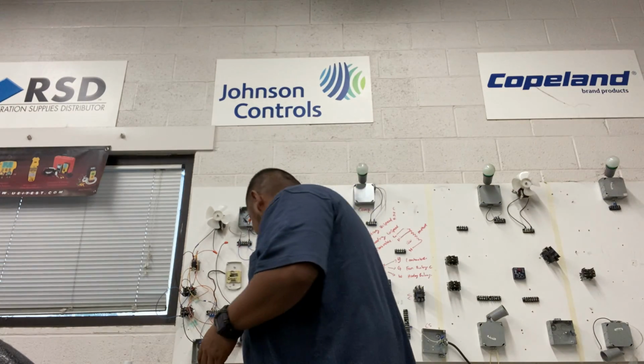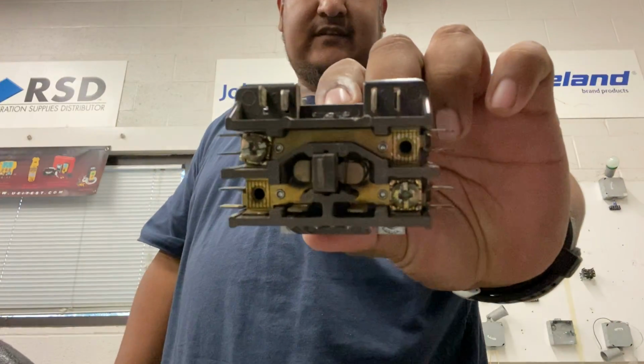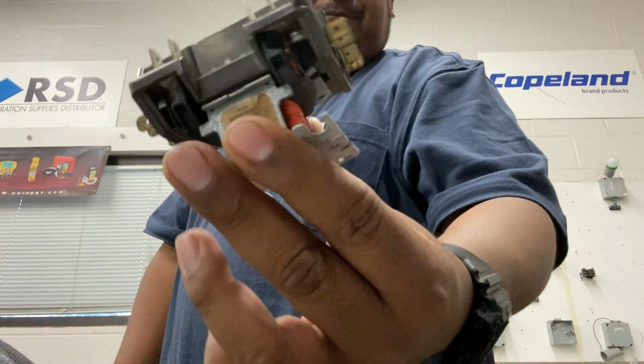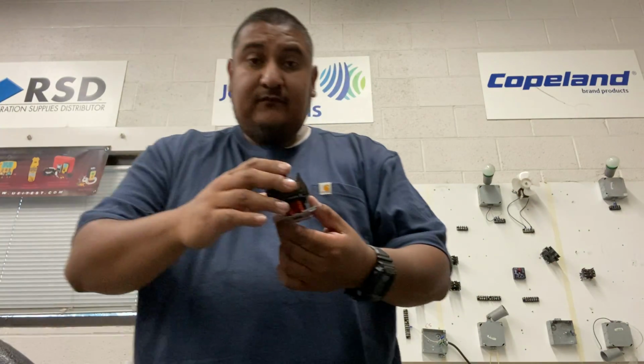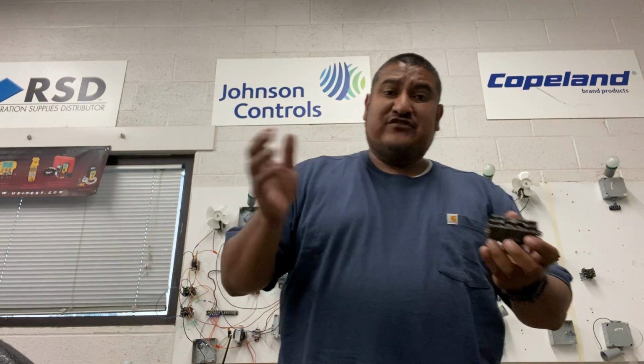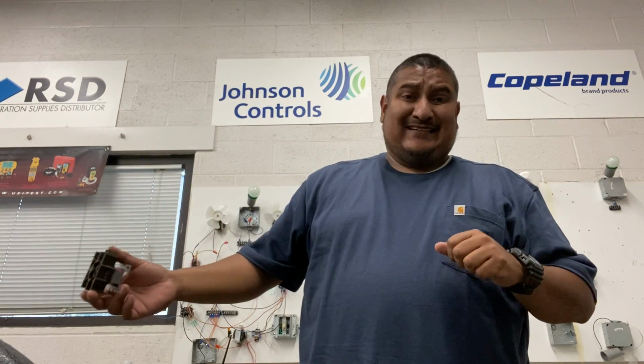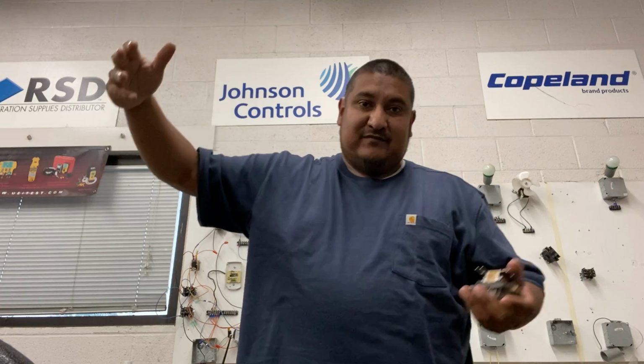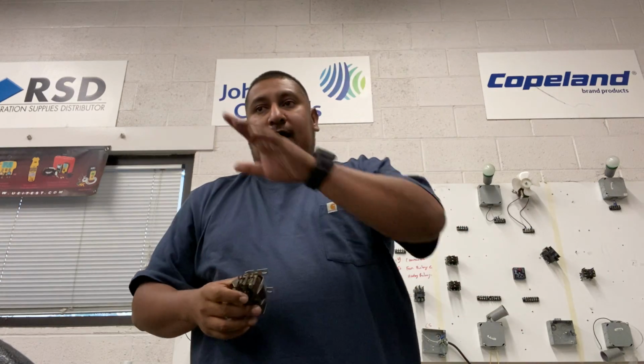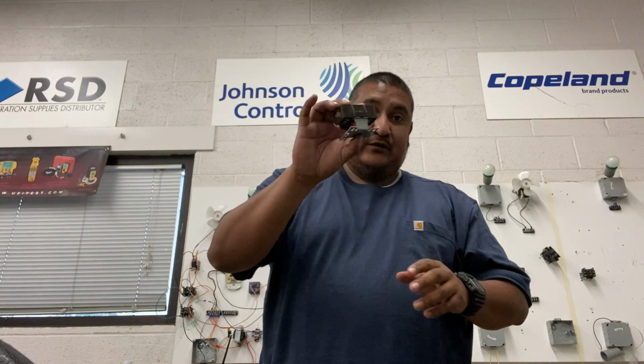So, first thing we're going to talk about is actually going to be this little guy right here. You guys can see that, right? There you go. This guy here is called the contactor, right? So the main purpose of the contactor is this guy is the one that receives the power, the incoming power, the 208 volts from a disconnect or its main power source, which is going to be PG&E. Right, so it comes into a disconnect, which is where we go, just as the name says, disconnect the power from the unit. That way we can isolate the unit and actually work on it safely. So after the disconnect, the first point is going to be this guy here.